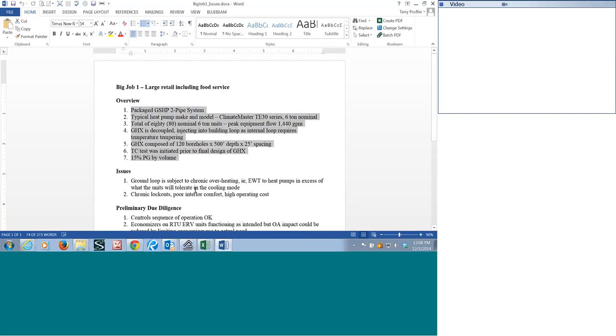Typical heat pump for this exercise is a 6-ton nominal Climate Master unit. We have a total of 80 of these units. Peak equipment load flow would be 1,440 GPM. This would be a decoupled system. That is, we're only going to inject into the loop field, into the building loop, when it needs to be tempered, which is a very efficient way to reduce your pumping costs. And the ground loop for this example is 120 holes, 500-foot depth by 25-foot spacing. We're also assuming a TC test was done prior to the final design and fairly low antifreeze content, 15% by volume.